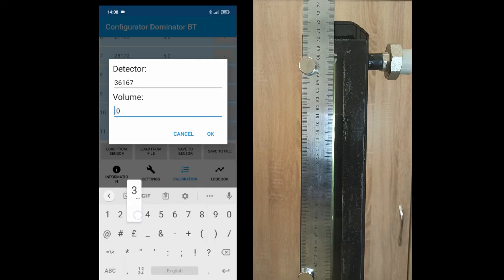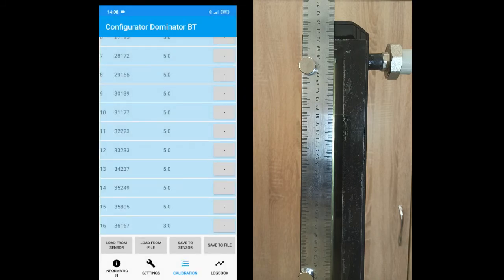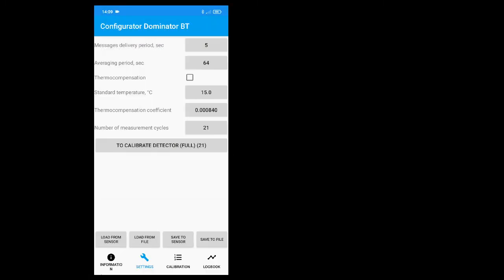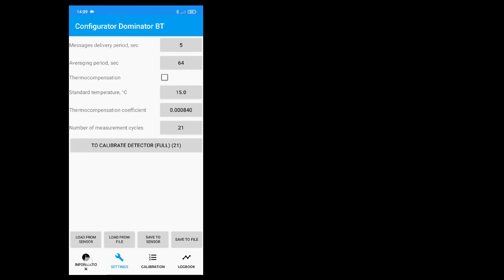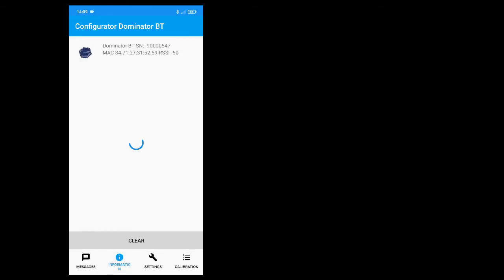After tank calibration is finished, save data to sensor. Change the averaging period constant to 32 or 64 to have smooth data, and save data to sensor. The sensor configuration is finished. Push the disconnect button to leave configuration mode.